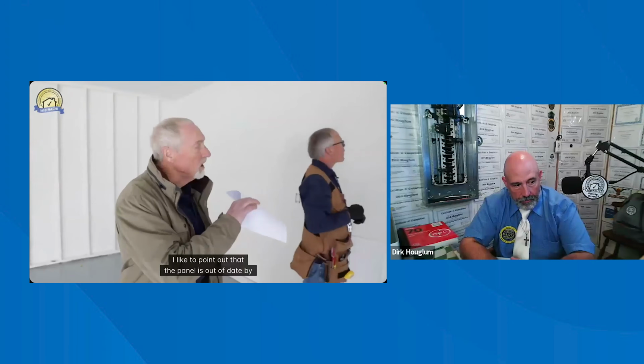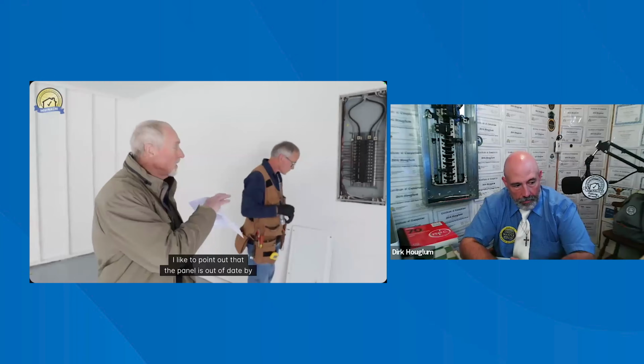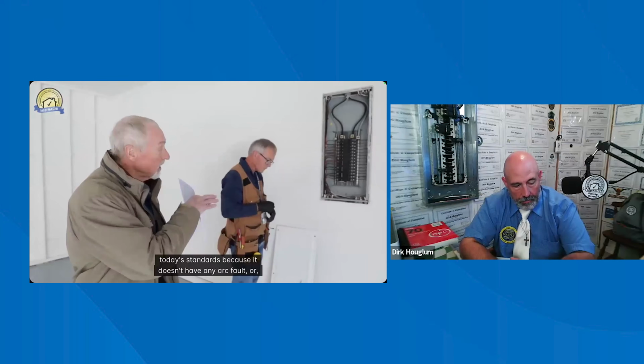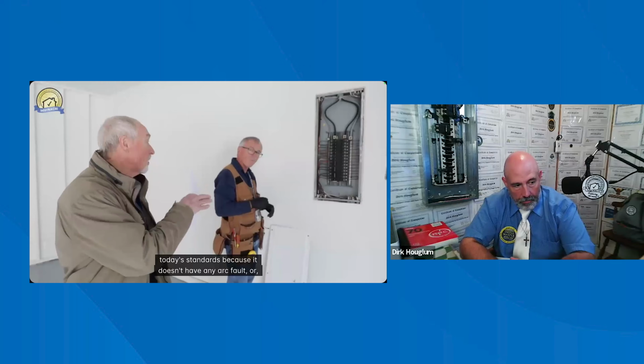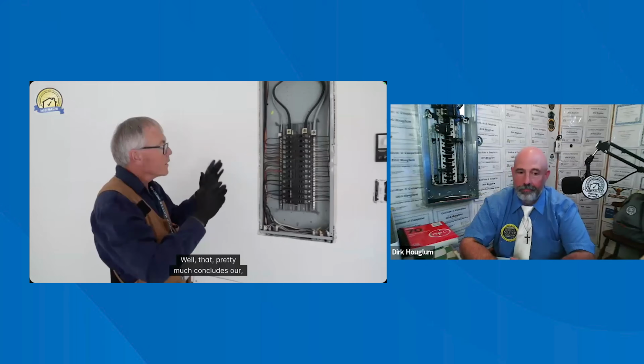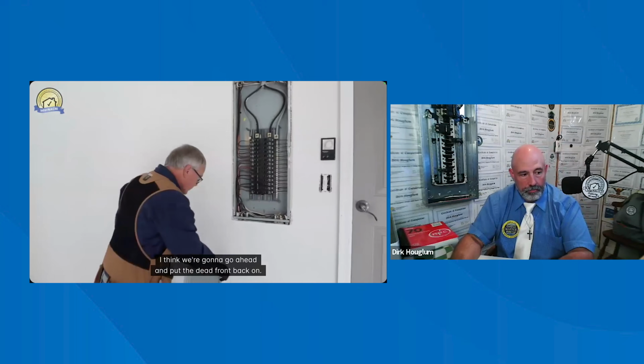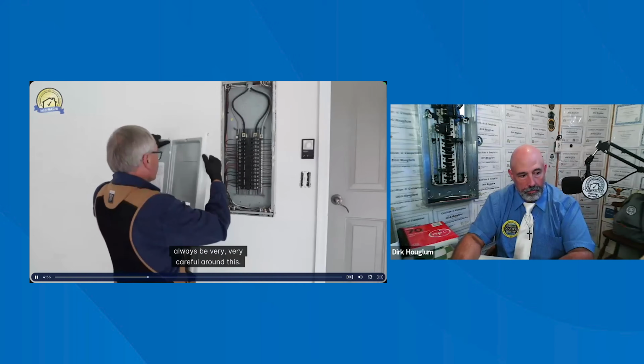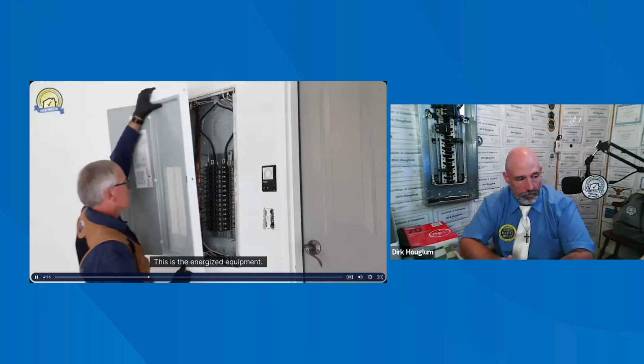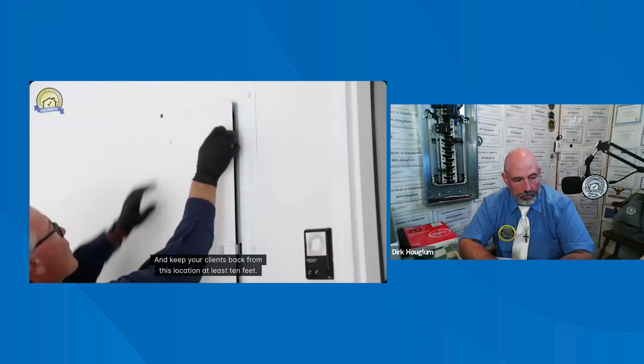I like to point out that the panel is out of date by today's standards because it doesn't have any arc fault or GFCI breakers in it, but there is no requirement to bring it up to today's standards. Well, that pretty much concludes our interior examination of the main panel. I think we're going to go ahead and put the dead front back on. And always remember the safety part of your inspections. Always be very, very careful around this. This is energized equipment, and keep your clients back from this location at least 10 feet.